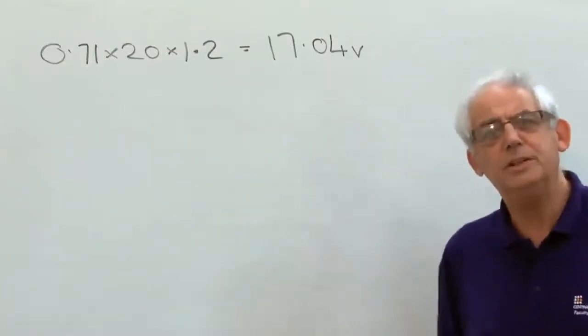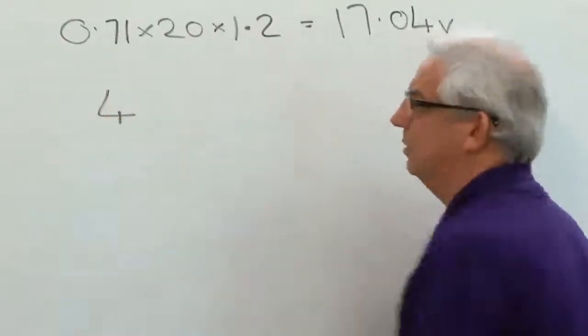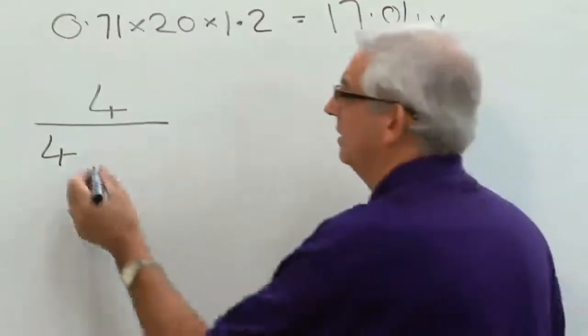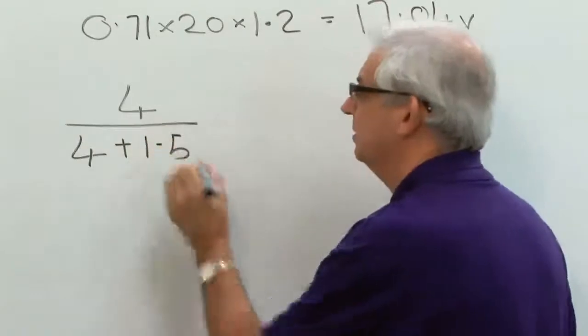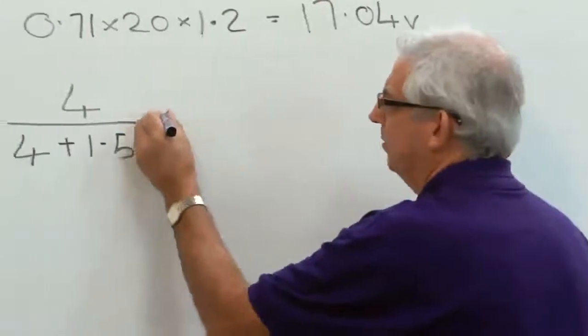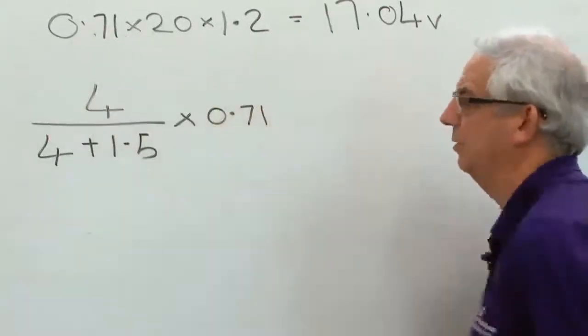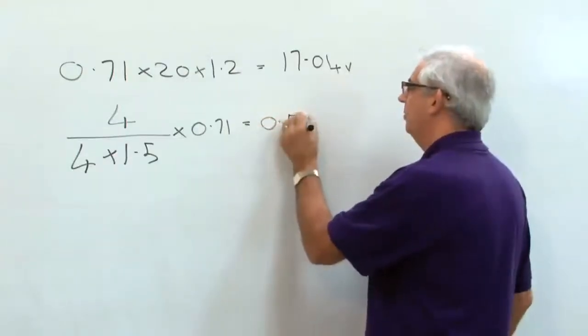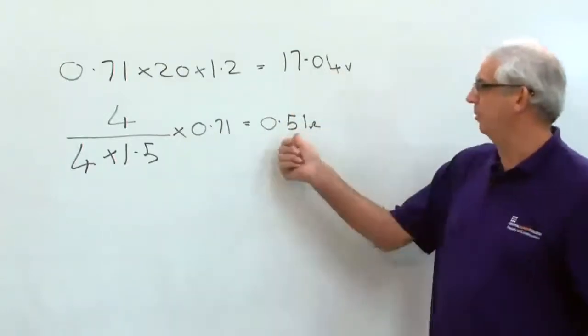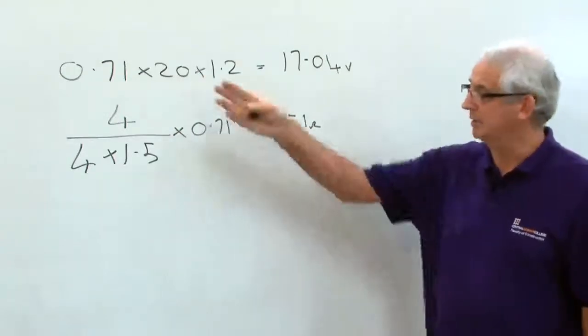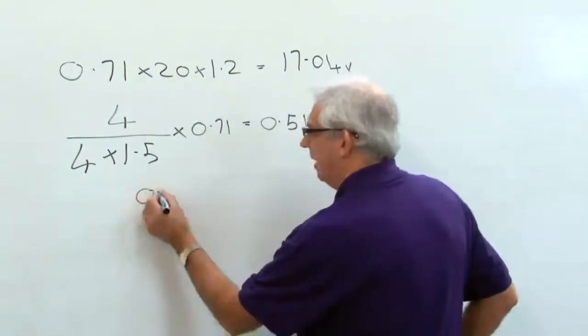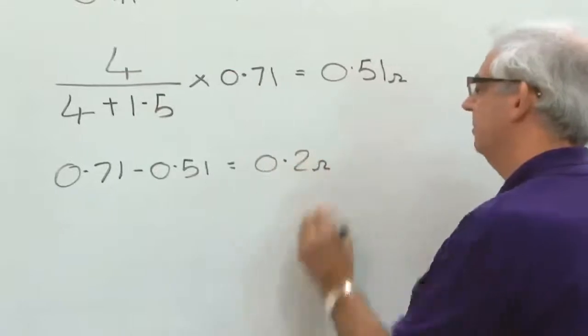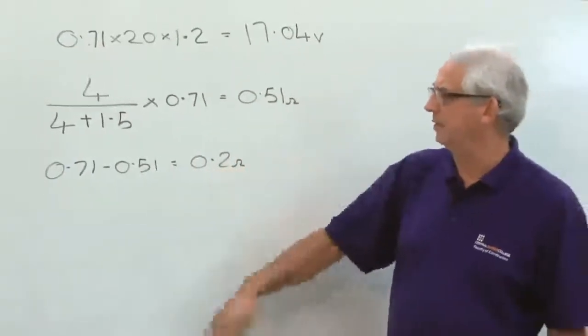It's quite a simple calculation. All I need to do is to divide the cross-sectional area of the live conductor or line conductor by the cross-sectional area of the line conductor plus the cross-sectional area of the CPC. I then need to multiply it by my R1 and R2 value, which I've got there. That's going to come out at around 0.51 ohms. This 0.51 ohms is the resistance of my CPC in this circuit. If I have an R1 and R2 of 0.71 and I take away 0.51, it gives me a resistance value of 0.2. 0.2 will be the resistance value of my line conductor.